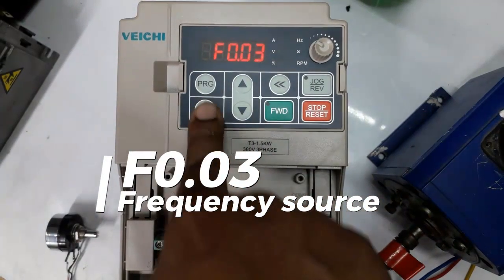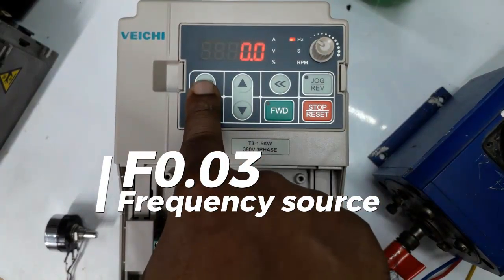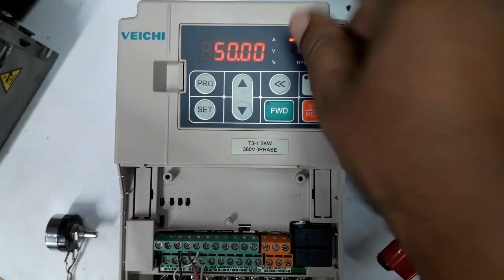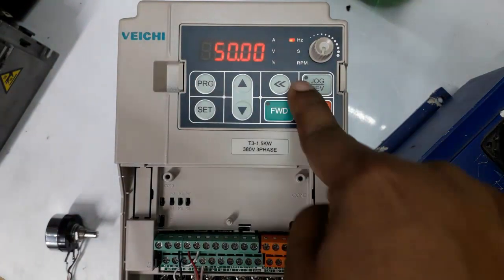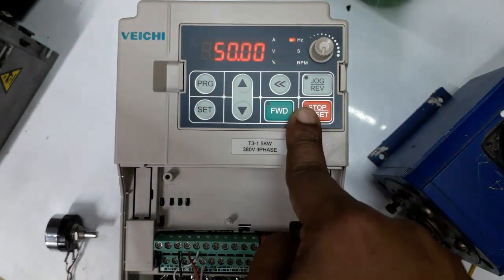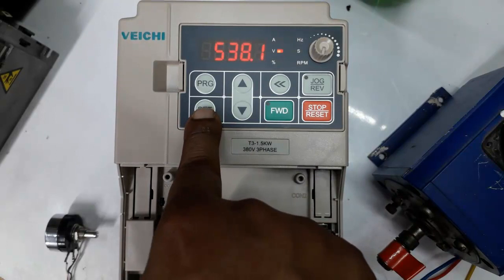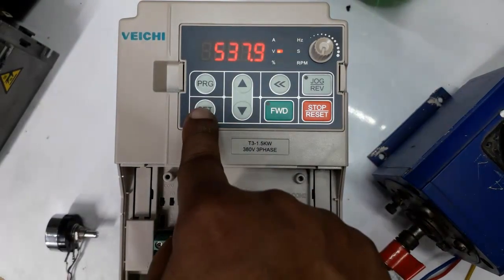F0.03 is for frequency source. We set it here to 1 for potentiometer, keyboard potentiometer reference. Now the drive is in 50 Hz setting.